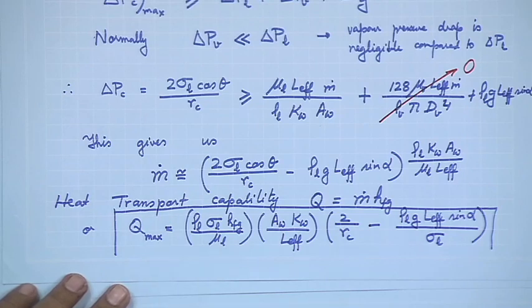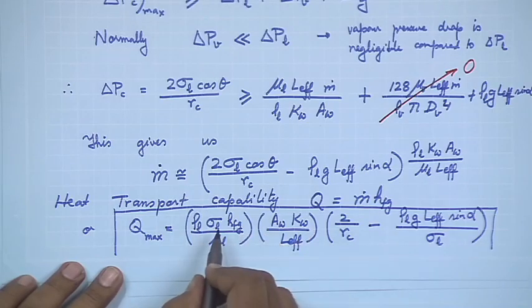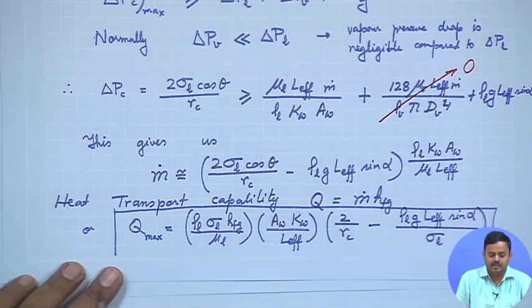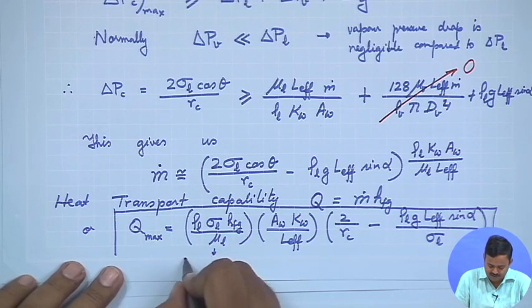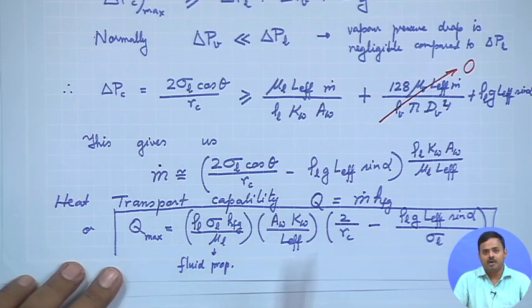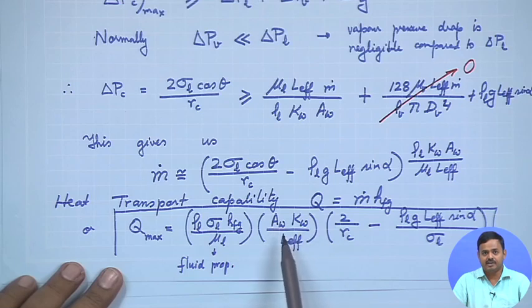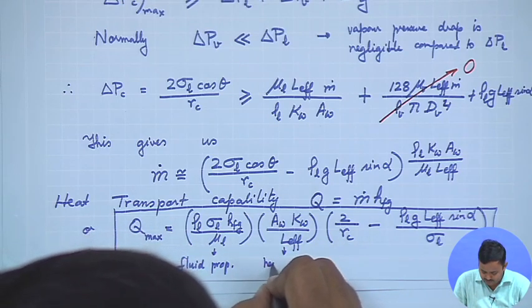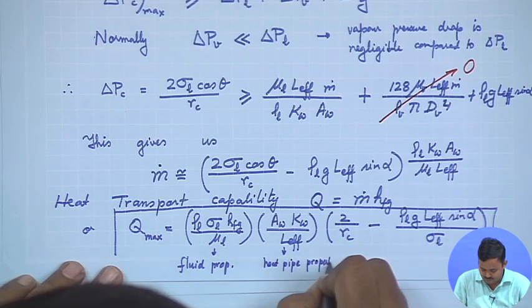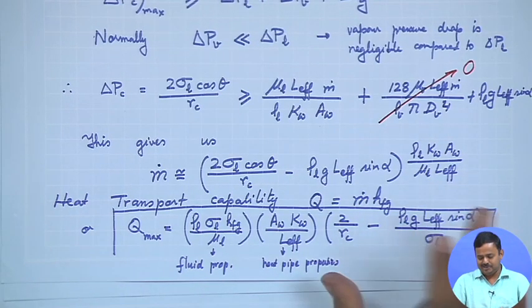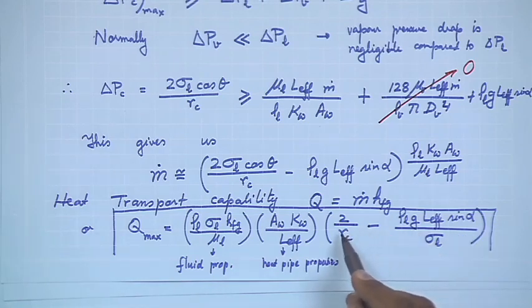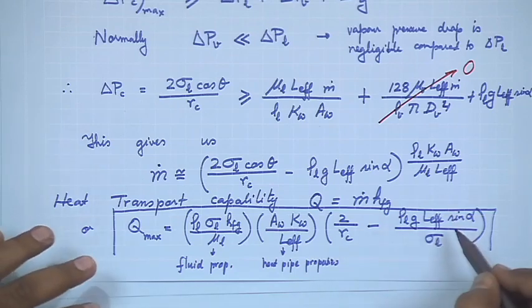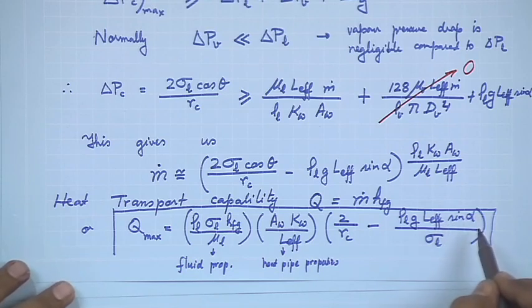This is a very nice expression. Looking at the first parenthesis: ρ_l · σ_l · h_fg / μ_l — these are all fluid properties. The second group, A_w · k_w / L_eff, contains the wick area, wick permeability, and effective length of the heat pipe — these are heat pipe wick and geometry properties. The remaining term involves a combination of fluid properties and geometric properties.